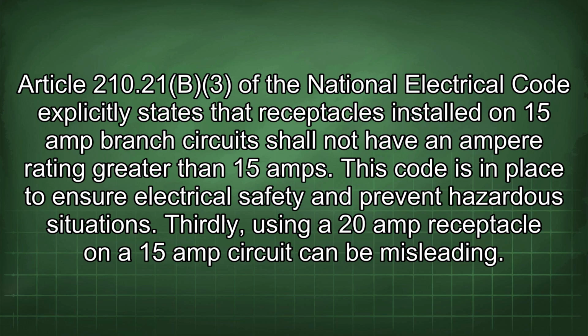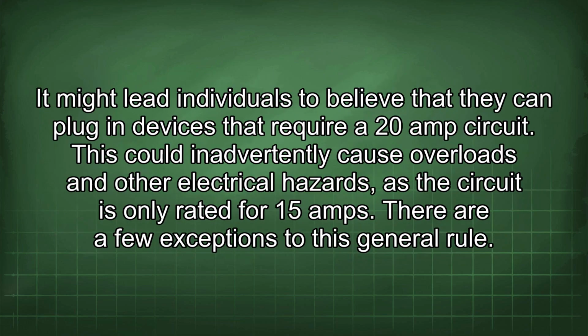Thirdly, using a 20 amp receptacle on a 15 amp circuit can be misleading. It might lead individuals to believe that they can plug in devices that require a 20 amp circuit. This could inadvertently cause overloads and other electrical hazards, as the circuit is only rated for 15 amps. There are a few exceptions to this general rule.